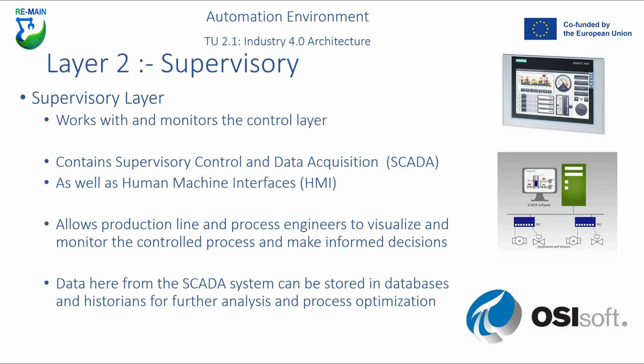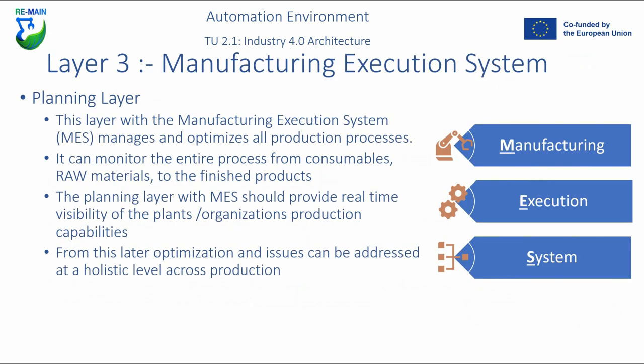Above layer one, layer two is the supervisory layer. This works with and monitors the control layer and is where you find your SCADA — supervisory control and data acquisition — systems as well as HMI systems. It allows production line and process engineers to visualize, monitor, and control the process and make informed decisions. Data from the SCADA system can be stored in databases and historians for further analysis and process optimization. As a user, this is the layer you may come into contact with the most.